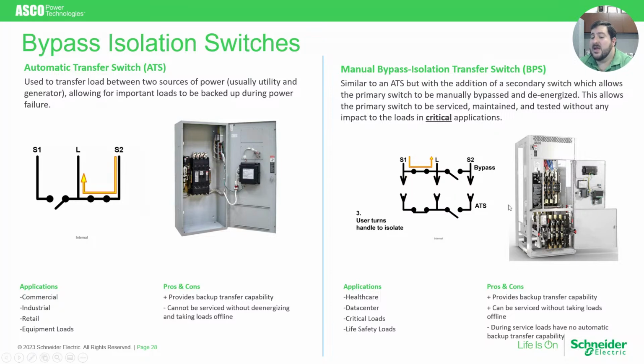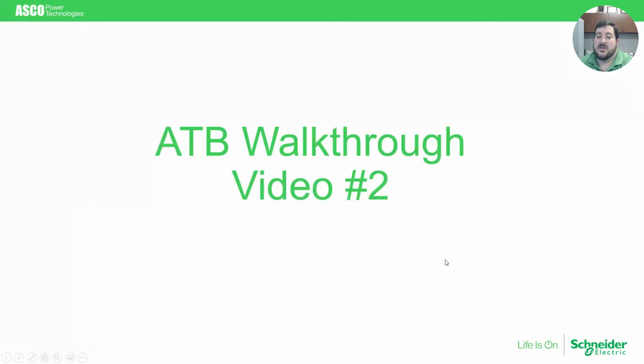So the way to do that is use a bypass transfer switch that allows you to bypass power directly to the load, de-energize the primary ATS completely, and do your service and maintenance on it without the load ever feeling an impact. And an extra bonus is that the extra handle on the bypass switch can also serve as an emergency backup should you want to manually operate the equipment as well. So to talk a little bit more and show a little bit more detail on the manual bypass isolation transfer switches, we do have another video where I'm going to walk you through one of those pieces of equipment.